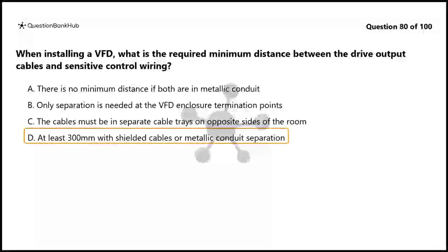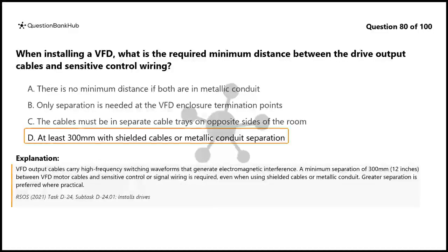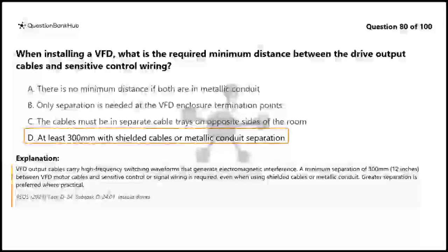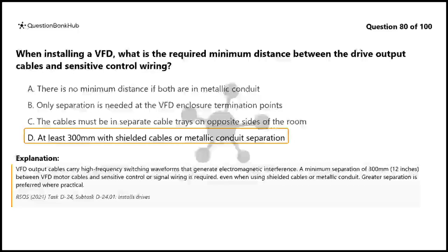The correct answer is D. At least 300 mm with shielded cables or metallic conduit separation. VFD output cables carry high-frequency switching waveforms that generate electromagnetic interference. A minimum separation of 300 mm, 12 inches, between VFD motor cables and sensitive control or signal wiring is required, even when using shielded cables or metallic conduit. Greater separation is preferred where practical.